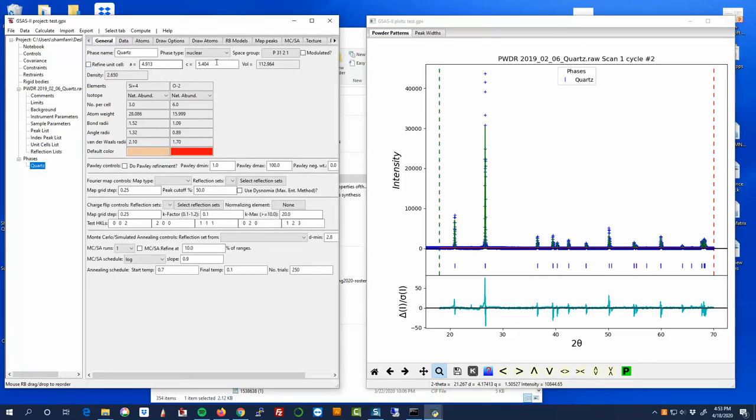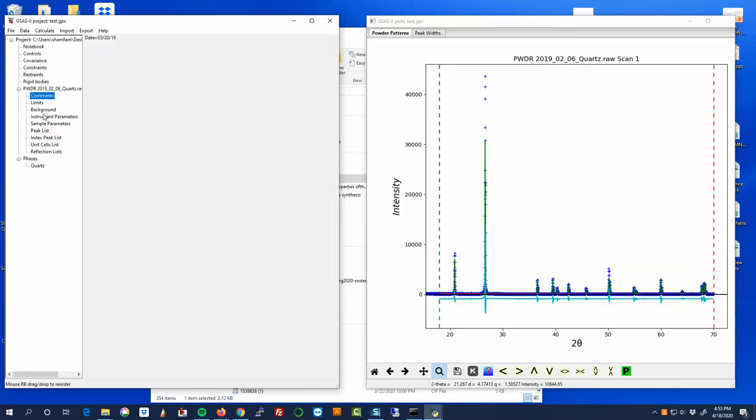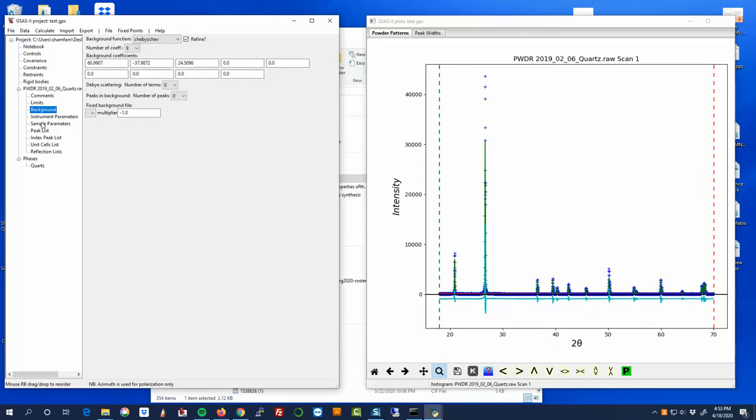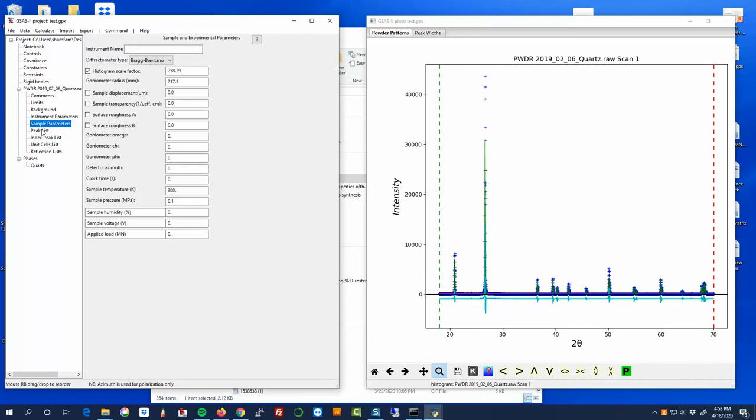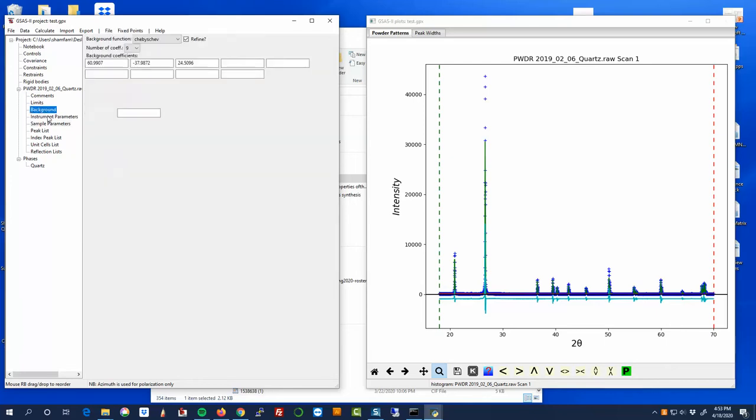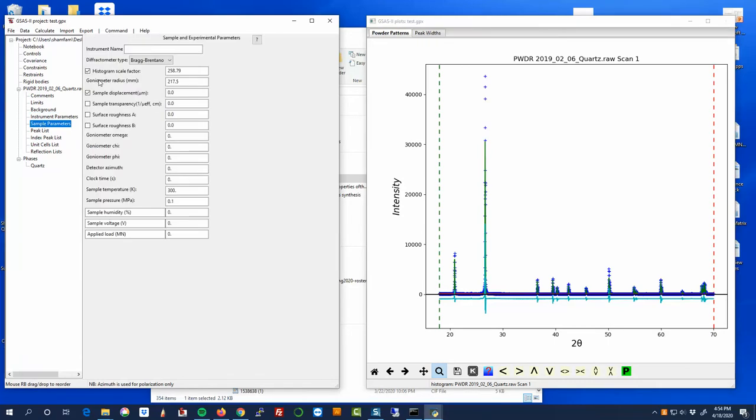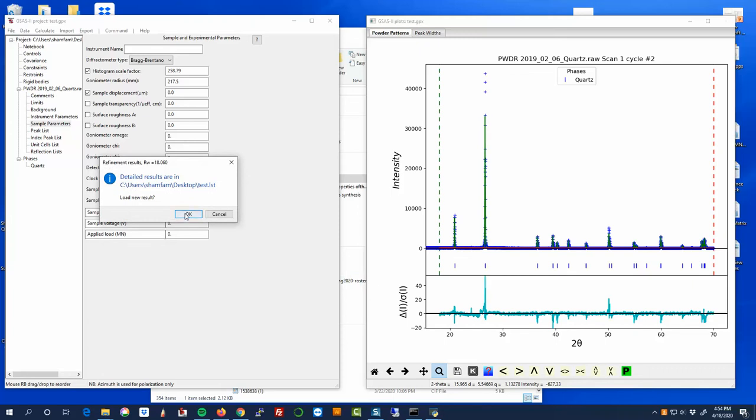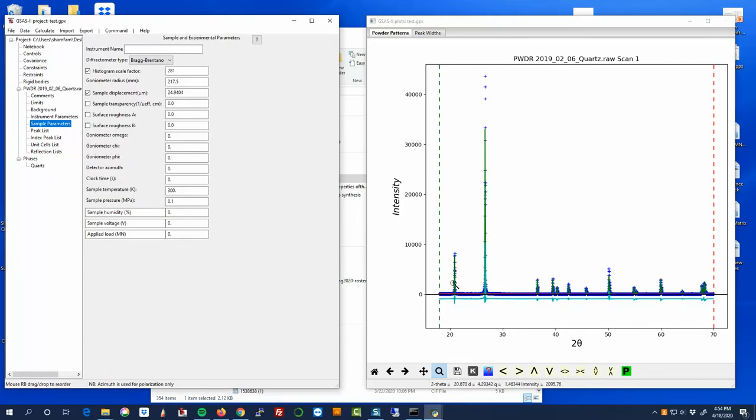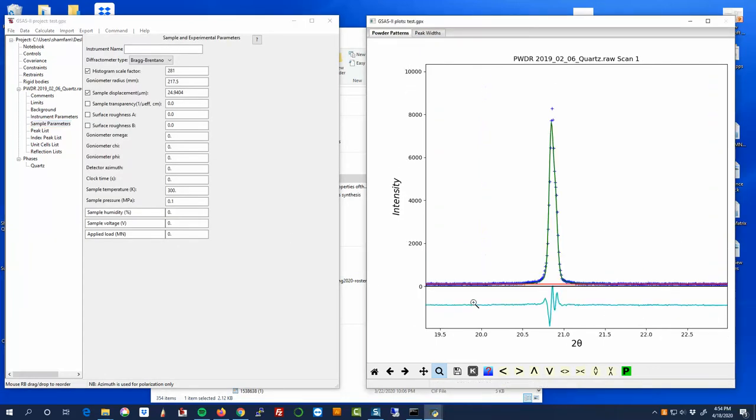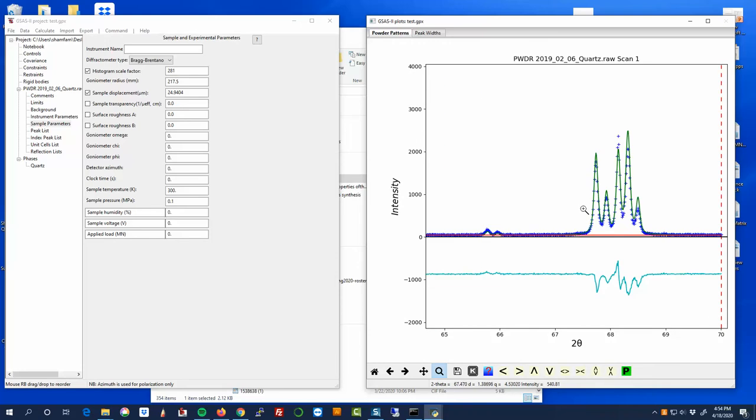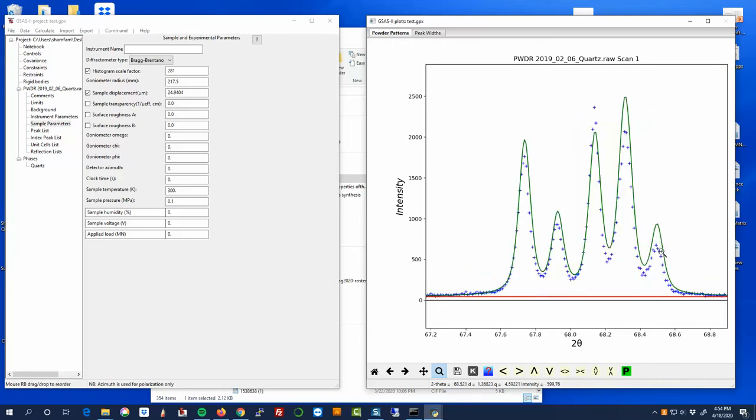So peak position is due to a couple things. It is due to lattice parameters, and so I can refine the unit cell. But even before that, I'm going to start off refining, let's see, background coefficients, sample parameters. So the scale factor I've already done, and I'm going to refine sample displacement. And so sample displacement is just talking about if the sample is not quite in the center of the goniometer. If it's a little bit higher or a little bit lower, that tends to shift all of those peaks. And so if we do this and we run refine, okay, we can already see that that did a lot better job taking care of that offset without even changing anything about the unit cell lattice parameters. See, so the peaks are a lot better aligned now than they were before.